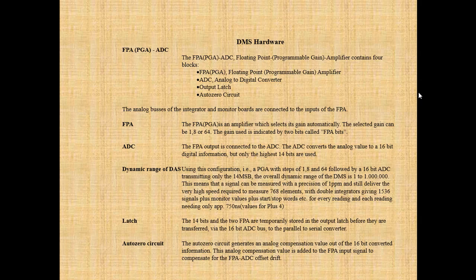The FPA/PGA is an amplifier that selects its gain automatically. The selected gain can be 1, 8, or 64, indicated by 2 bits called FPA bits. The FPA output is connected to the ADC, which converts the analog value to a 16-bit digital value, but only the highest 14 bits are used. Using a PGA with gain steps of 1, 8, and 64 followed by a 16-bit ADC transmitting only the 14 MSB, the overall dynamic range of the DMS is 1 to 1,000,000.